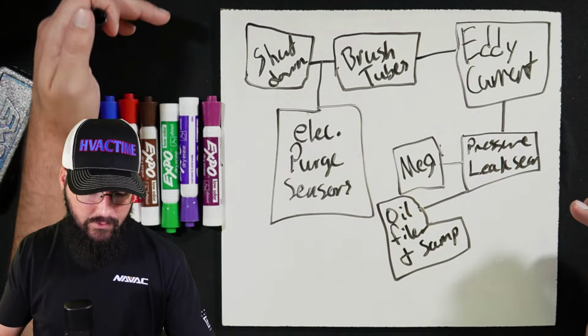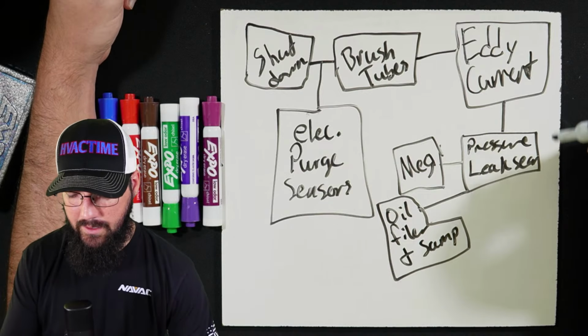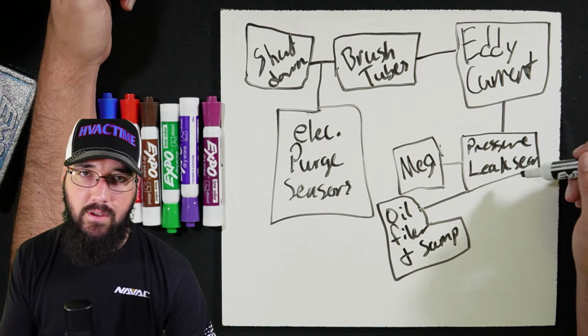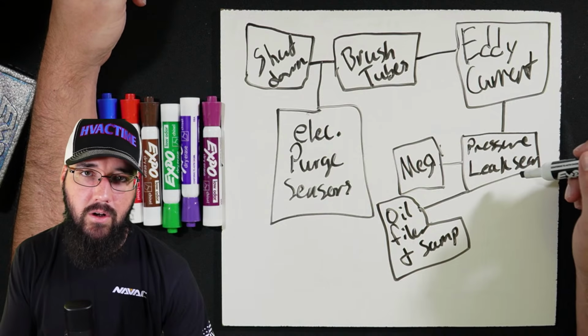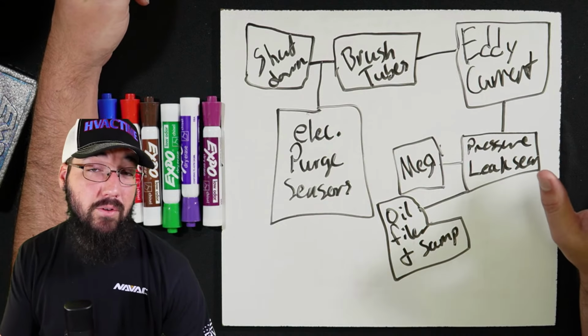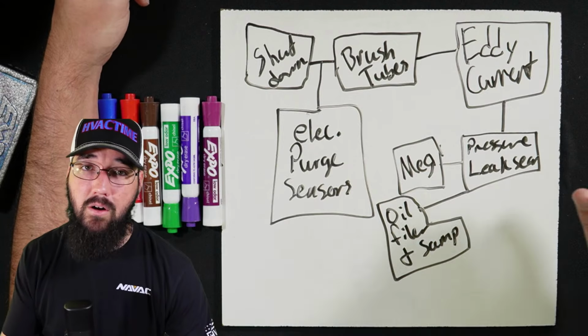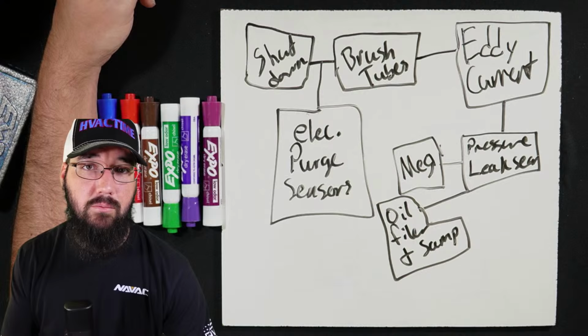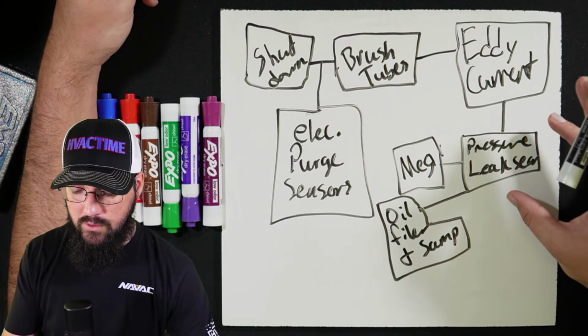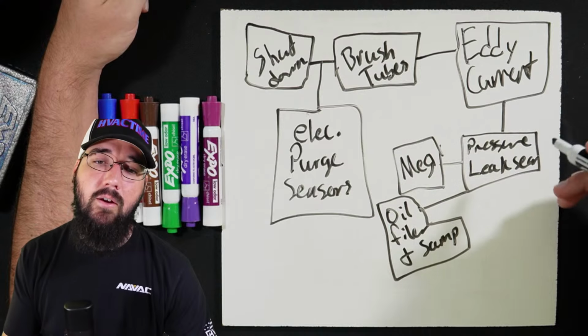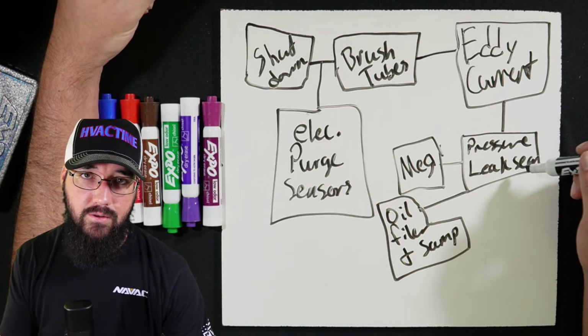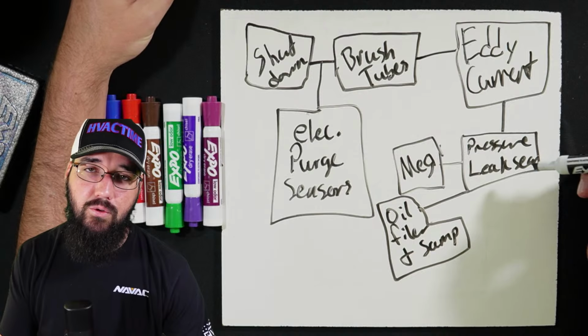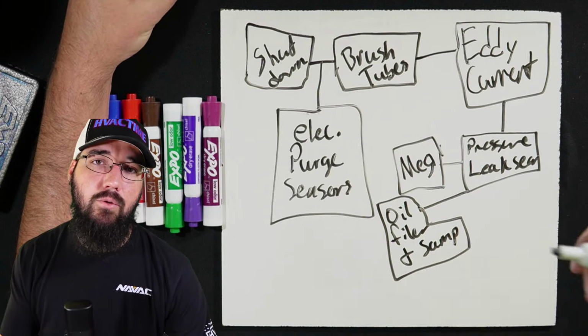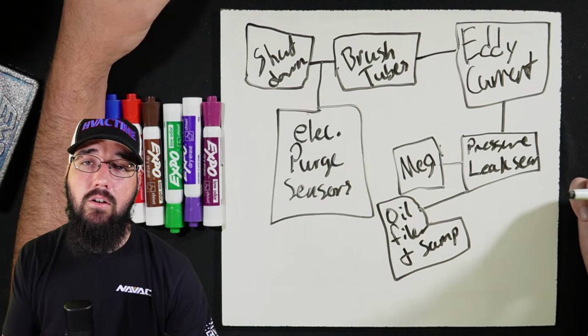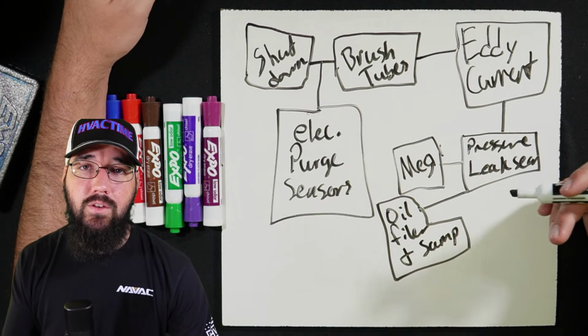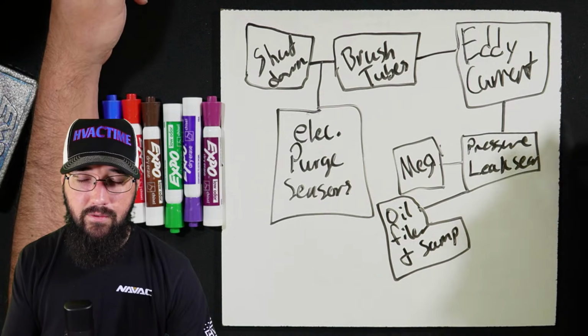If you're not pressurizing, you're not going to get a successful leak search. There's just no point in trying if you're not able to pressurize. I don't care what method you use for pressurizing, whether it's hot water out of the tap or an actual pressurizing machine. Try to pressurize. If you can't pressurize, you're not going to be able to properly get a leak search. Just not going to happen. At that point, you're solely relying on your purge unit to give you feedback on the pump outs and trusting the purge to actually be working correctly.